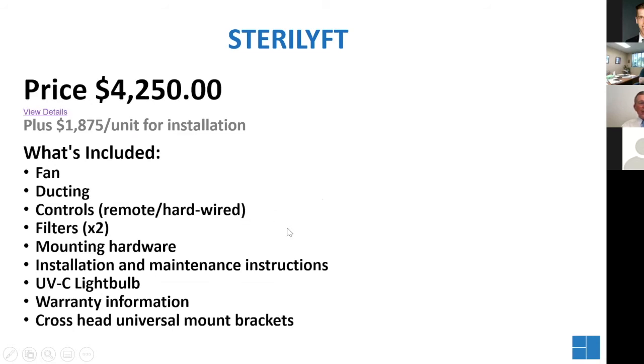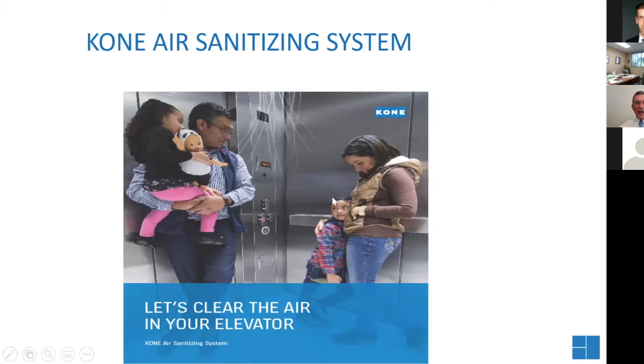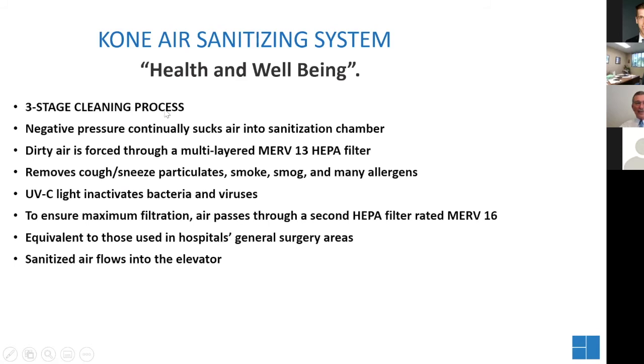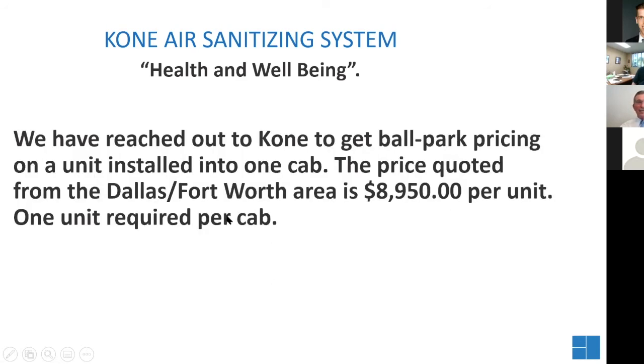Remember that all this information is available to the managers on SharePoint. They'll be able to access all this information for future needs. So Kone also has their own system. The Kone system is called Health and Wellbeing. It's a 3-stage system where it sucks air into a sanitation chamber, goes through a MERV 13 filter, is hit with a UVC light, and then the sanitized air flows back into the elevator. We reached out to Kone. The price of that is about $8,950.00, and it requires 1 unit per cab.